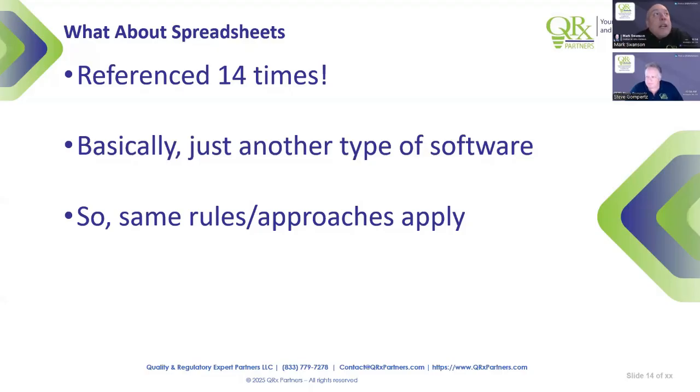Because we have a little bit of time here, Steve, I just want to again emphasize this. If you put a formula in there, you can hand calculate the result of what your entry is. Then you can just make sure that the spreadsheet comes up with the same result as what you hand calculated. You have now validated it. Magic. As long as you don't change that, then your validation is done for all time for that one.